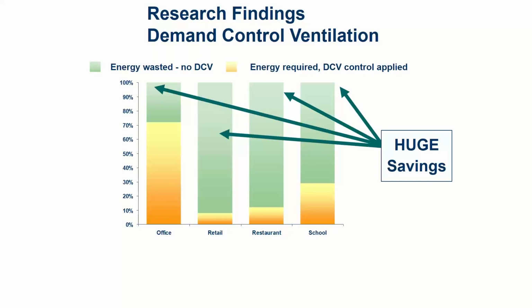Schools see a big reduction too, coming from multiple reasons. One, your classroom might be designed for 35 kids, but you only have 27 this year, so there's eight kids I don't have to ventilate for. In the summertime, I'm either not running the class or have reduced hours and occupancy, so I'm saving there too. But the really big piece comes from the fact that in a normal school built in the 1980s or later with ventilation, I ventilate each room for the design occupancy, but those people aren't in the room all day.